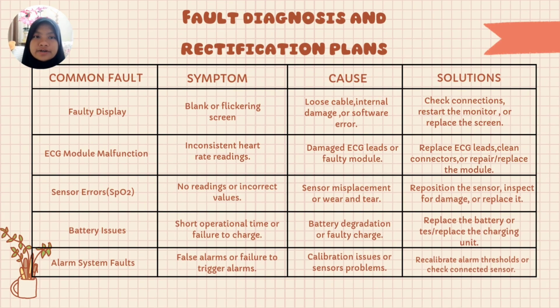For the fault diagnosis and rectification plan, there are 5 common faults here. First common fault is faulty display. The symptom is blank or flickering screen. This is caused by loose cable, internal damage, or software error. The solution is to check connection, restart the monitor, or replace the screen.